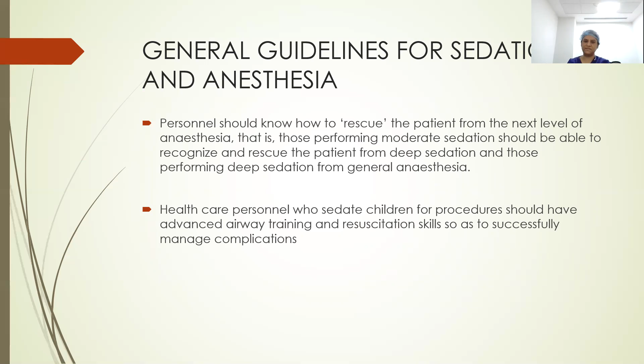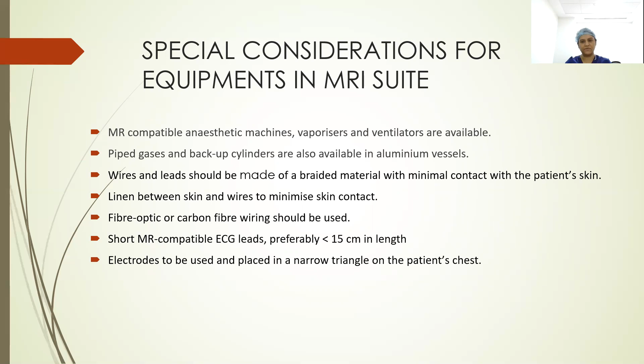What are the special considerations for equipment in the MRI suite? MR-compatible anesthetic machines, vaporizers, and ventilators are available. Piped gases and backup cylinders are also available in aluminum vessels. Wires and leads should be made of a braided material with minimal contact with the patient's skin. There should always be a linen between the skin and the wires to minimize skin contact so as to avoid burns. Fiber optic or carbon fiber wiring should be used. Coming to the ECG leads, short and MR-compatible ECG leads, preferably less than 15 centimeters in length, should be used, and electrodes should be placed in a narrow triangle on the patient's chest.